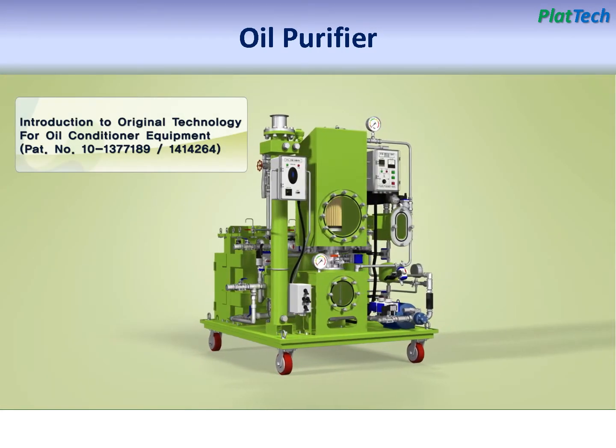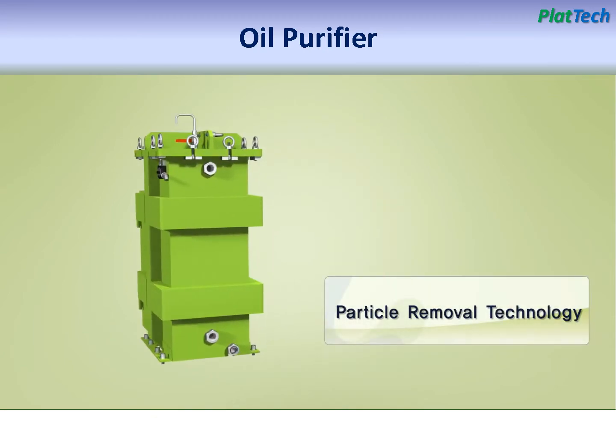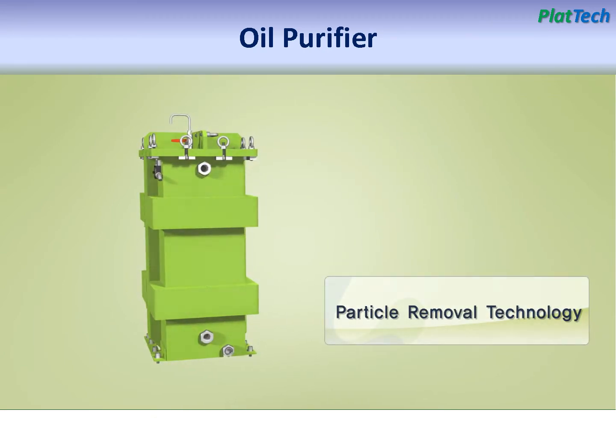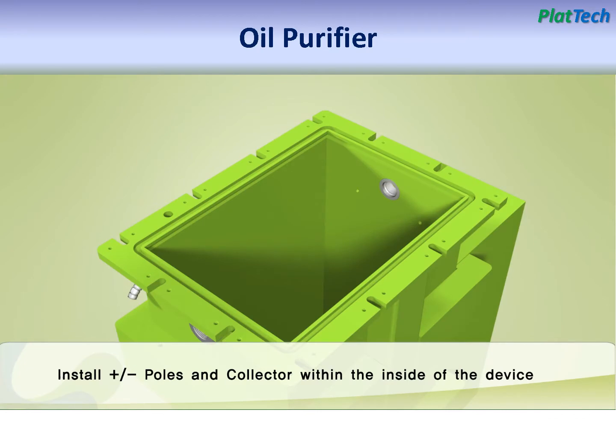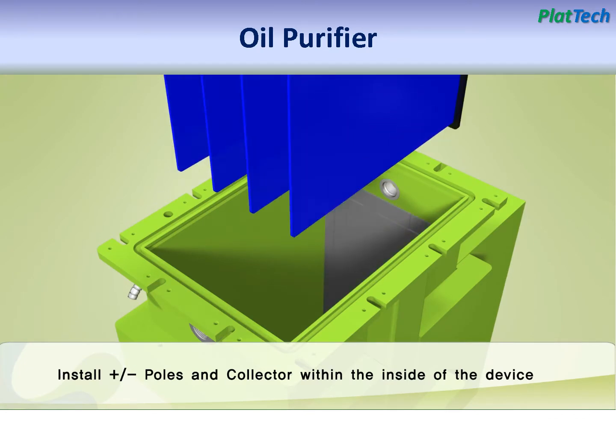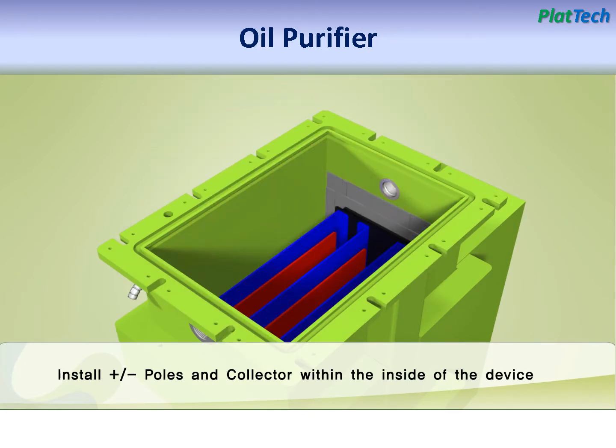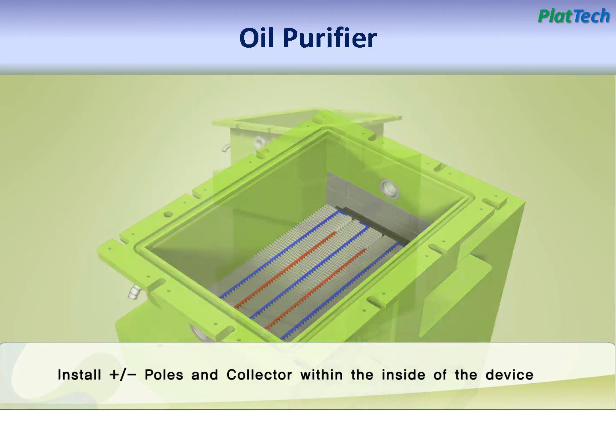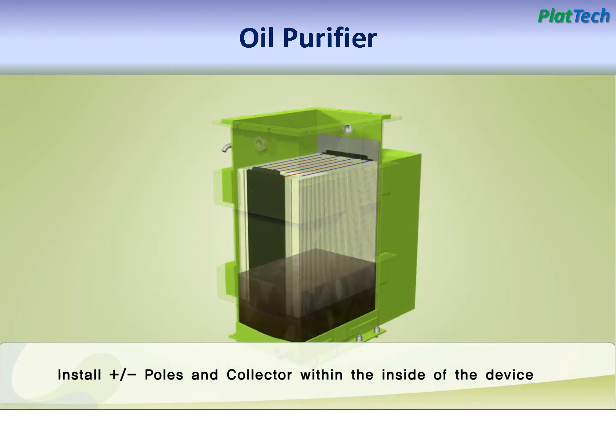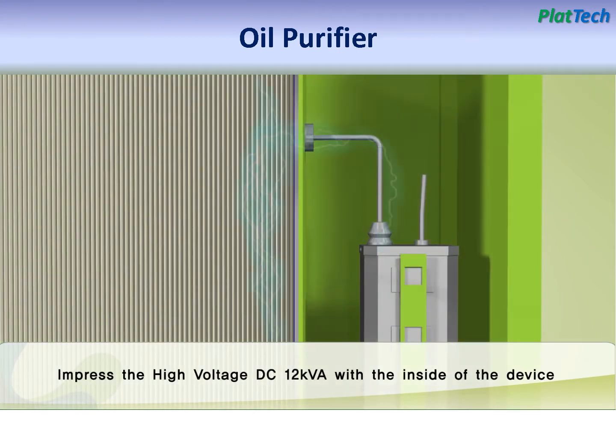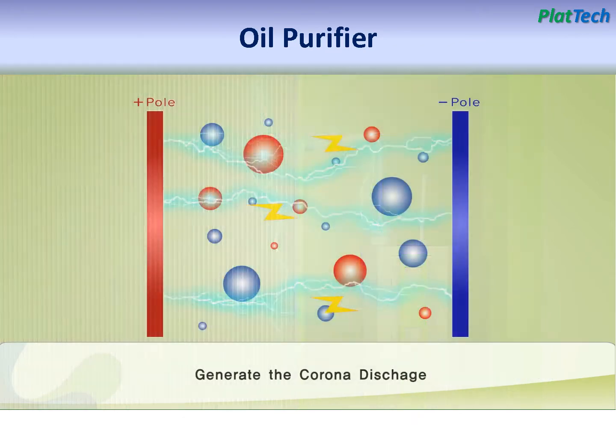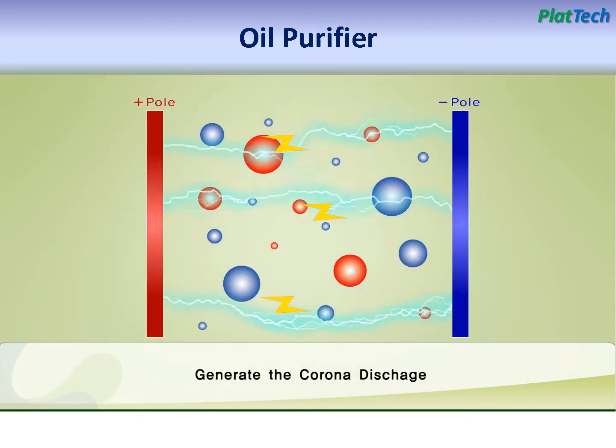The oil purifier has enhanced compact design. For particle removal section, the electro-absorption filter uses electrostatic technology with high voltage. Anode and cathode poles and specially designed filtering media are equipped. After feeding contaminated oil, high voltage will be supplied from the transformer, and corona discharge effect will take place.